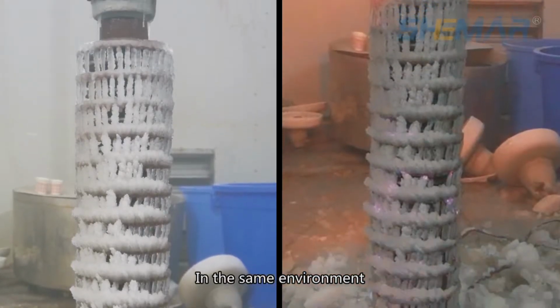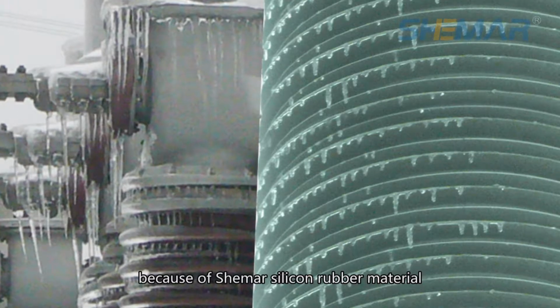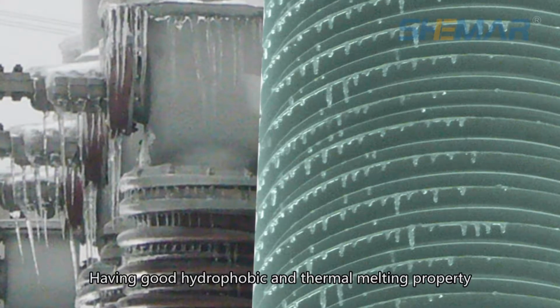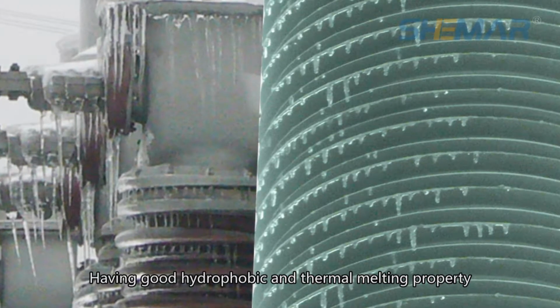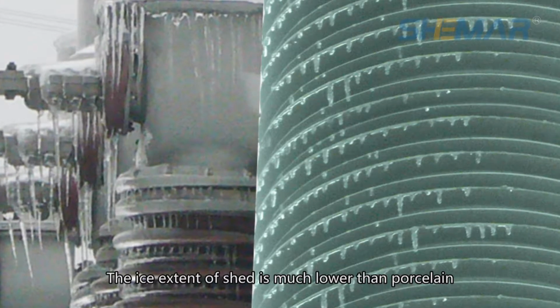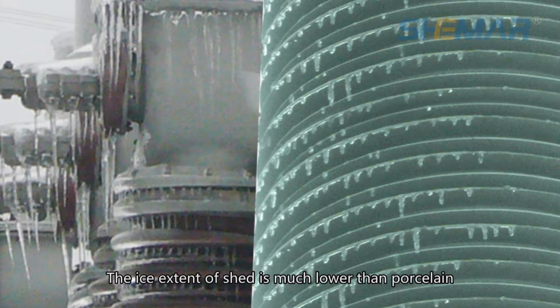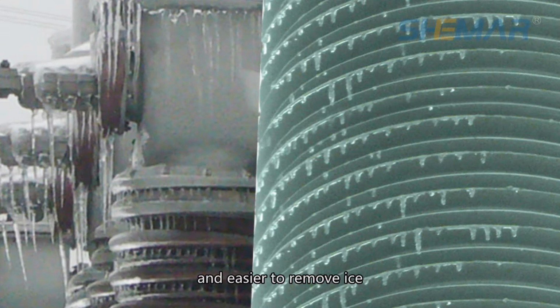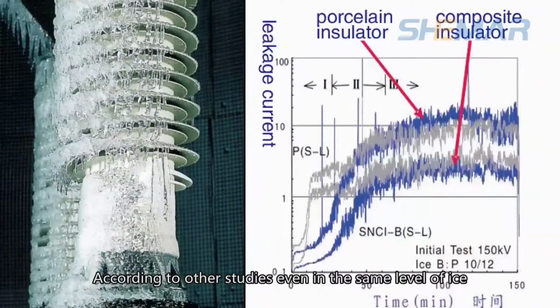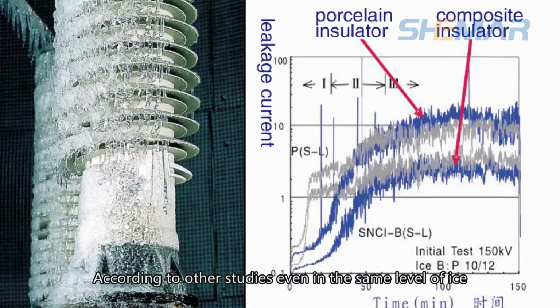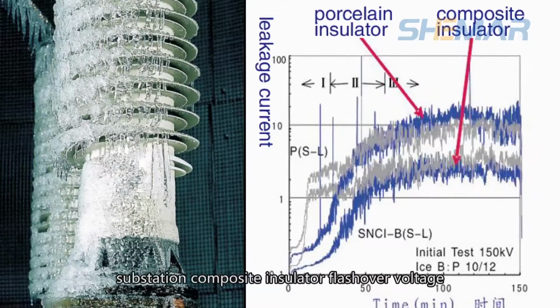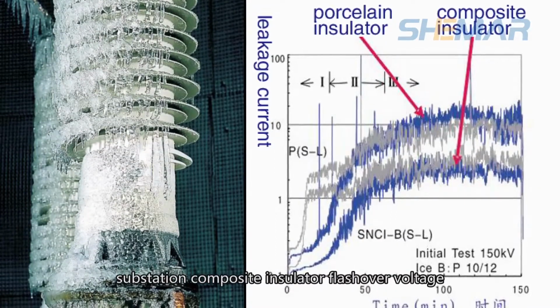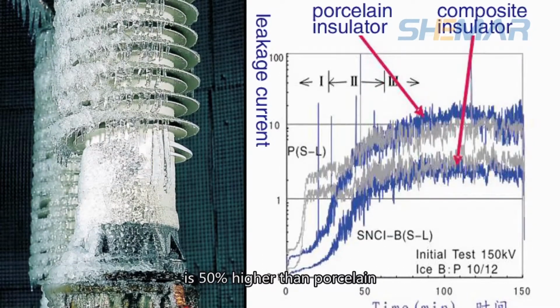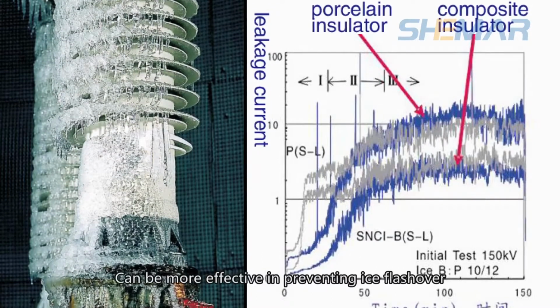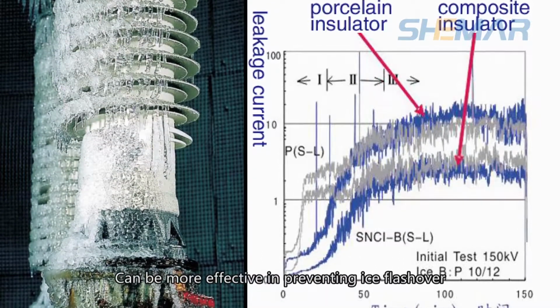In the same environment, because SHEMAR's silicone rubber material has good hydrophobic and thermal-melting properties, ice accumulation on the shed is much lower than porcelain and easier to remove. According to studies, even at the same level of ice, the flashover voltage of composite insulators is 50% higher than porcelain, making them more effective at preventing ice flashover.